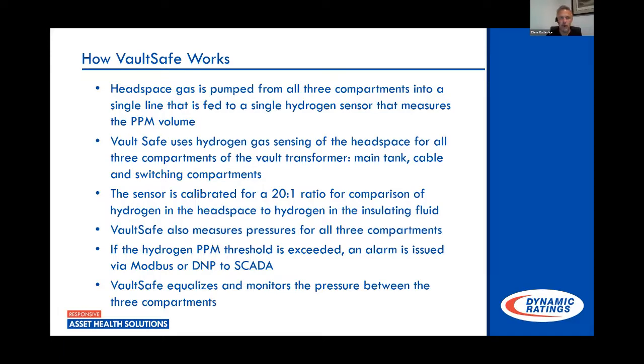So the thought was, we'll take the headspace and we can manifold these compartments together and run all this gas through a sensor chamber that's built within the monitor that lets us measure for hydrogen values. Also, since all 3 compartments' gas spaces are manifolded together, it allows us to do one pressure check as well.